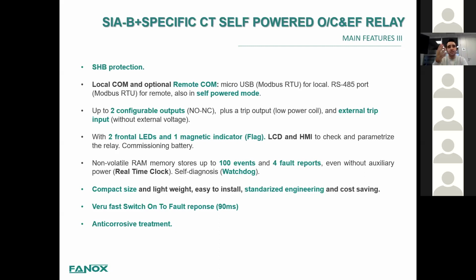There is another issue, the two more important features that we have: up to 2 configurable outputs, plus the dedicated trip output for the low power coil, and an external trip input, which works with no need for external voltages. That is very, very important. It's a free potential contact. You just need an oil temperature indicator from the transformer or any other device that can close a contact, and the relay will trip instantaneously. Again, we have two frontal LEDs for indication and one magnetic indicator also.